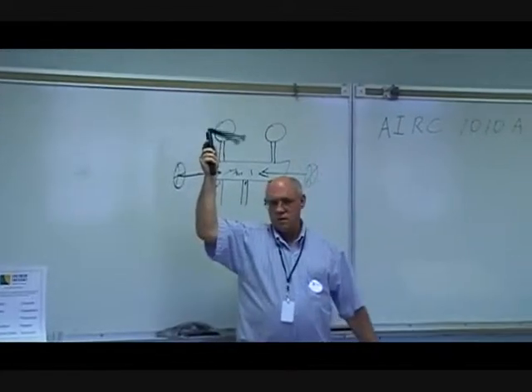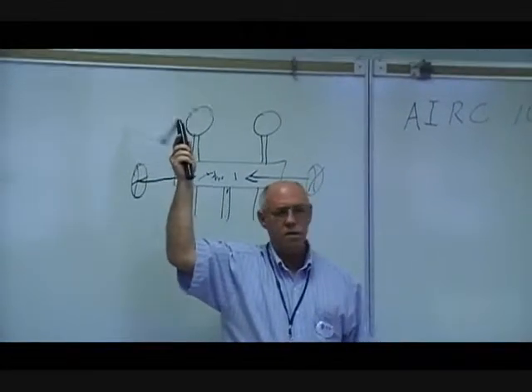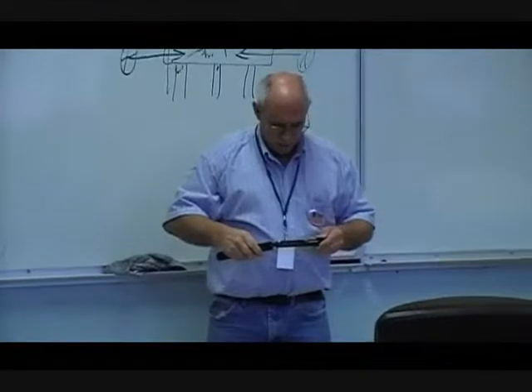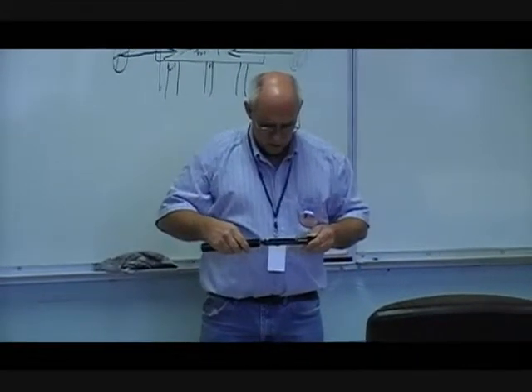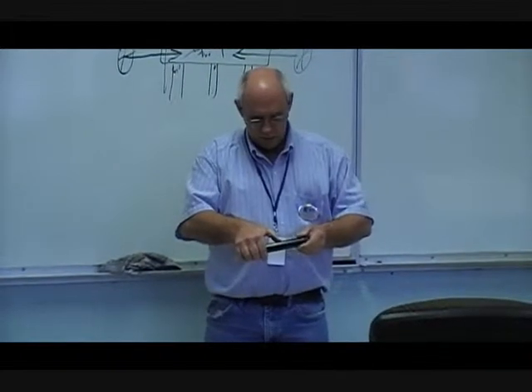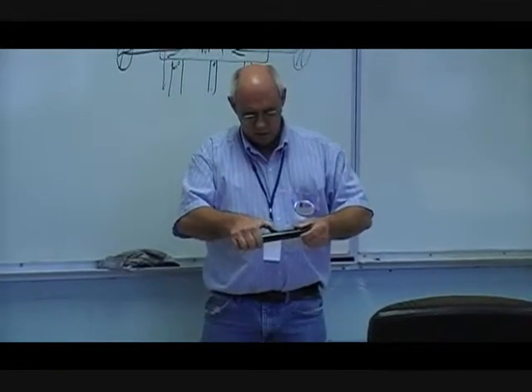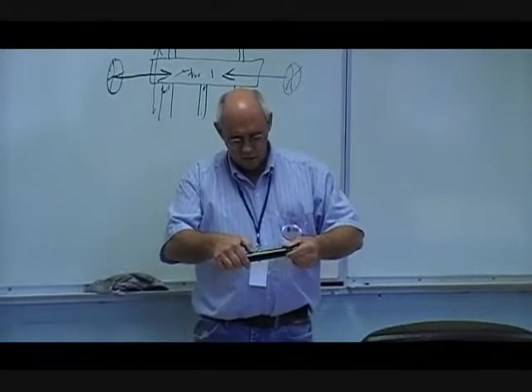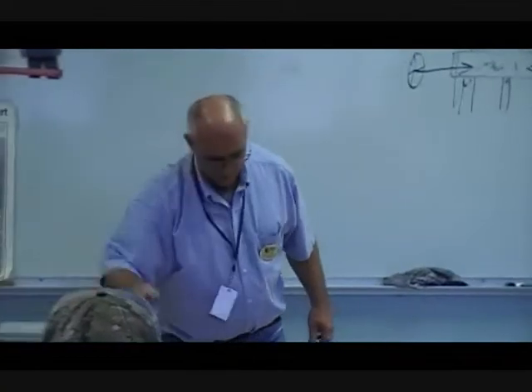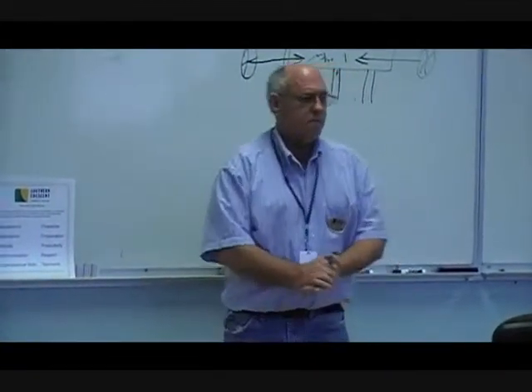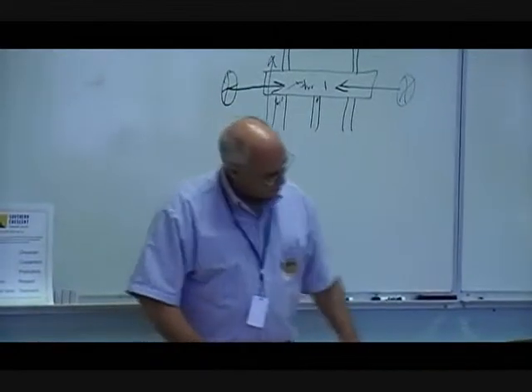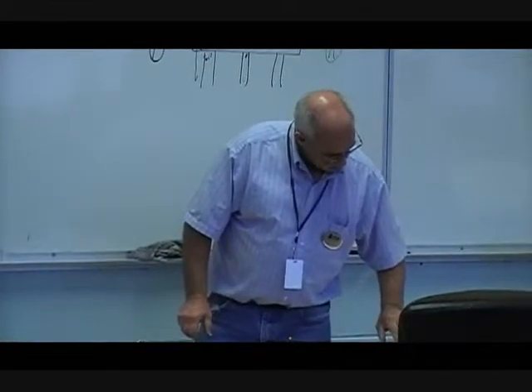It could be just a small can that had air in it, or it could be a small room, or it could be an entire city where the air is pretty much the same, the characteristics are the same. In reading so, I find out that my wet bulb is 58 and my dry bulb is 72. Now, this particular sling psychrometer has a scale on it that I can go to and tell you what the RH is, 58 and 72. I have kind of a dry day. It's about 45 percent in here. Want to pass that around so you can look at it? Preferably, we see somewhere around 50 percent, 50 to 55 percent in most houses or places where people are. It's a little bit on the dry side. Not bad, but a little bit on the dry side.